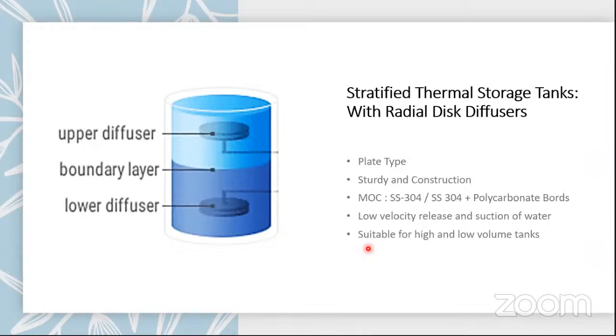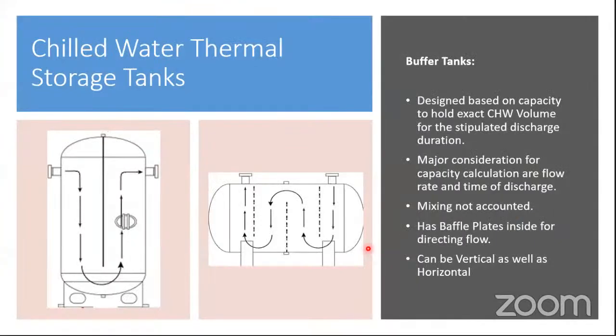By both the tanks, I mean that one is where you have long hours of discharge, as long as 8, 9 hours, and they are huge non-pressurized tanks. And the other category is used for the backup duration, let's say for 5, 10 minutes, where they are pressurized closed tanks. They can be termed as low volumes. We will understand them separately in the slides to come.